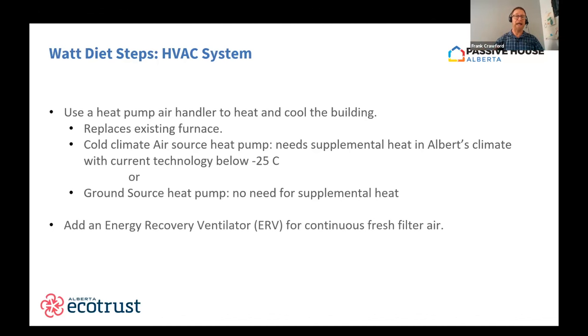We want to add an energy recovery ventilator. This provides continuous filtered fresh air. An energy recovery ventilator is similar to a heat recovery ventilator, HRV, except the energy recovery ventilator also recovers the moisture. So you get a bit of moisture and heat recovery, and that moisture recovery is really good in our dry Alberta climate.